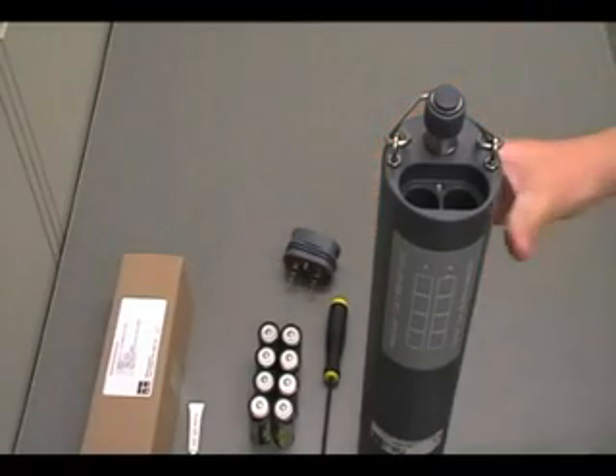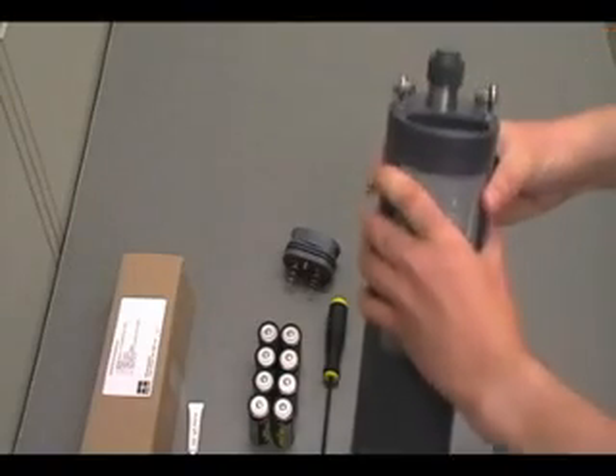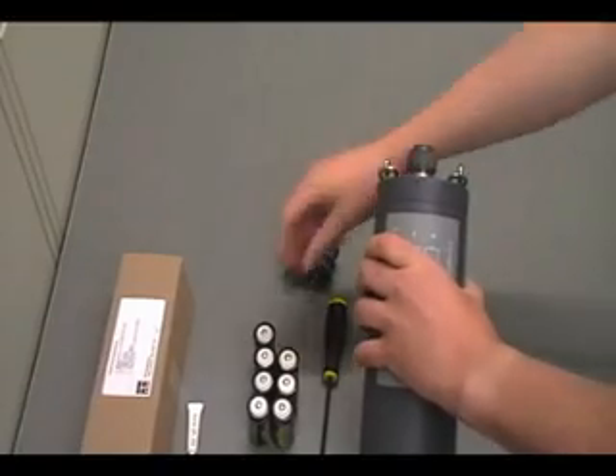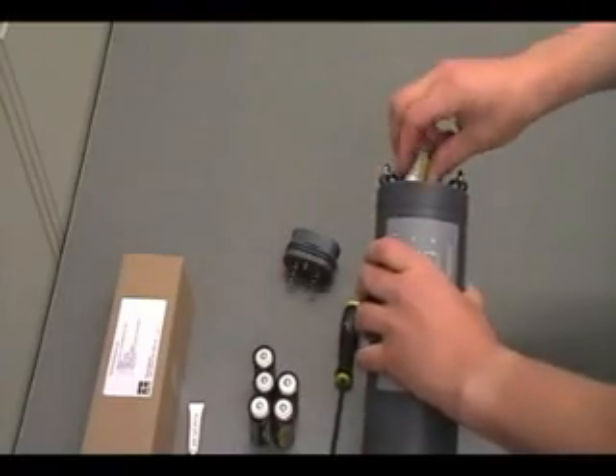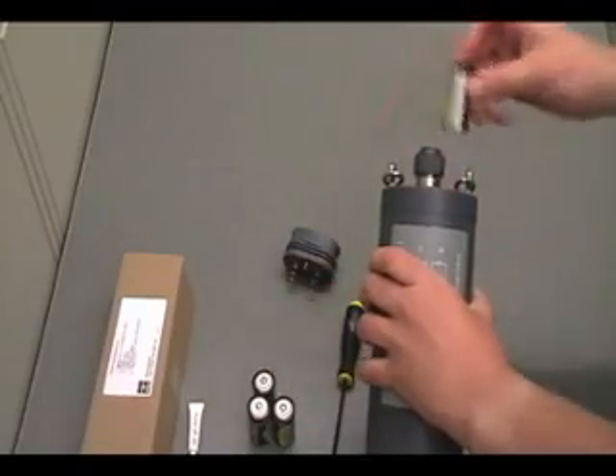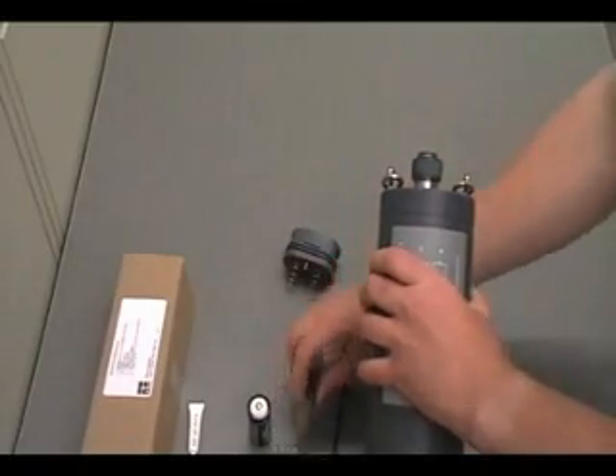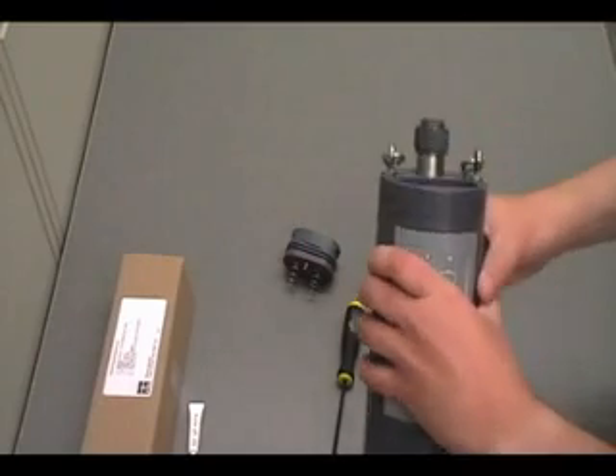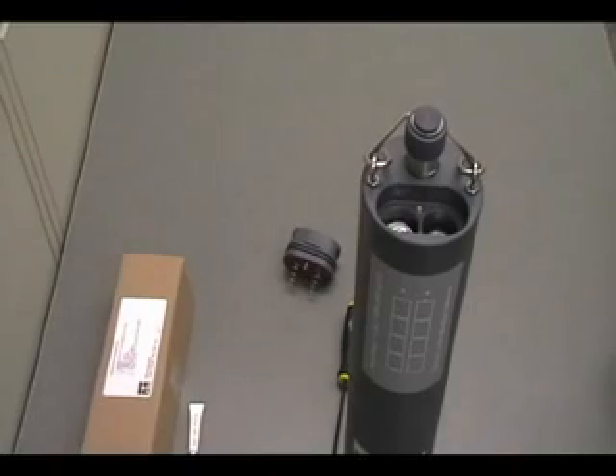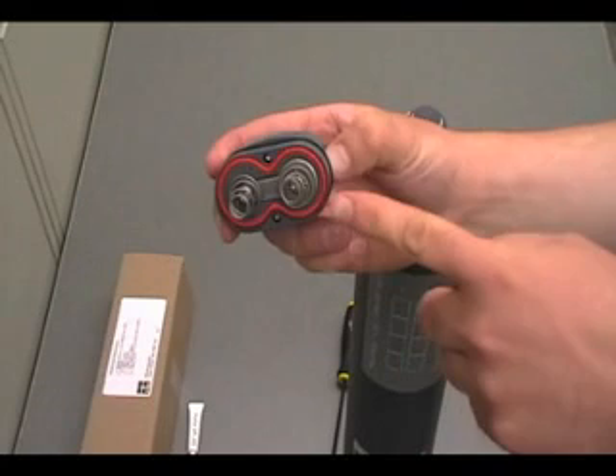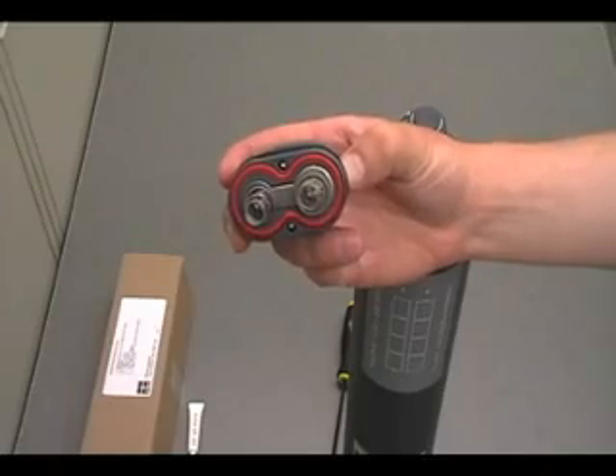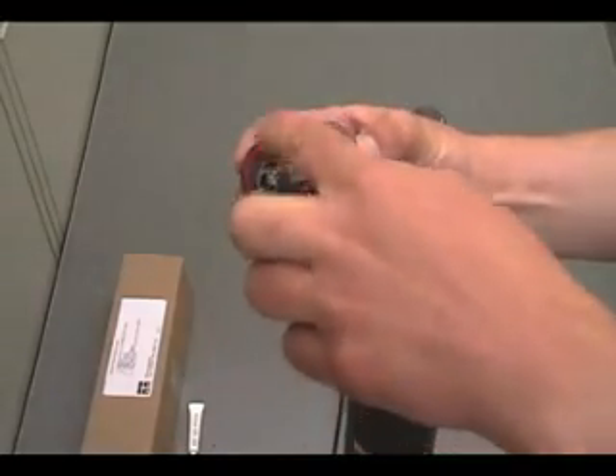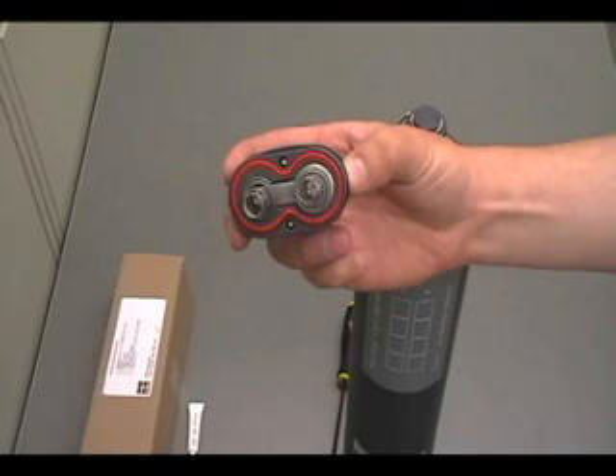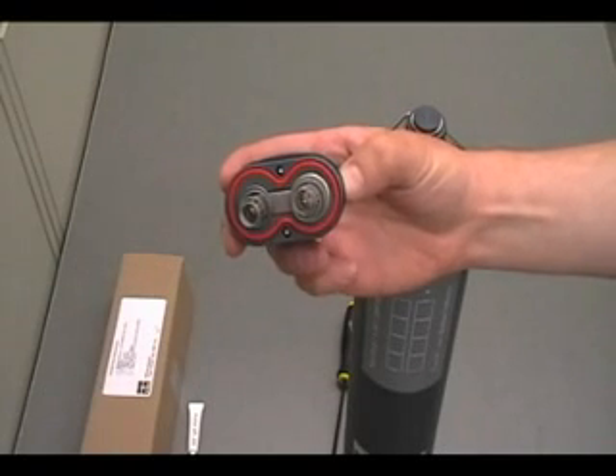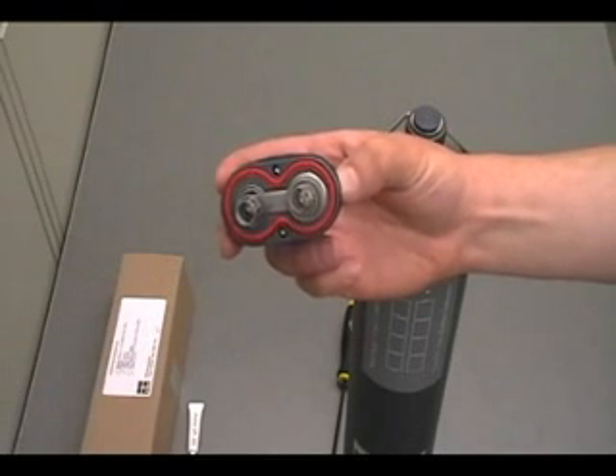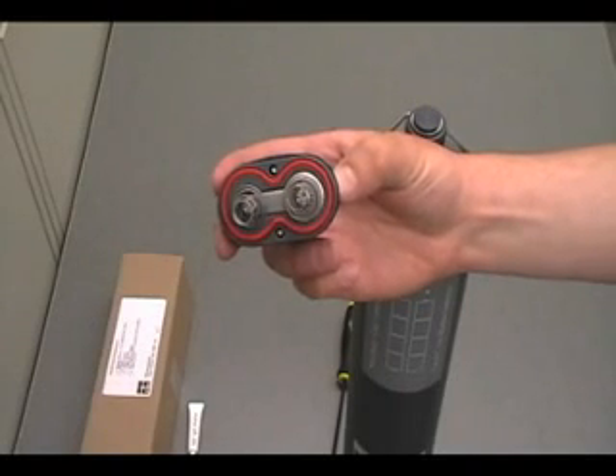Install the batteries as shown on the guide. Ensure that they have the proper orientation. Step 3. Before replacing the lid, it is important to ensure that the orange O-ring is seated completely within the groove on the underside of the lid. Press around its edges to make sure it is not popping out of the groove anywhere along its length. Small retaining tabs along the O-ring help keep it inside the groove. There is a detailed description of how to properly seat this orange O-ring on pages 219 to 220 of the YSI instruction manual. Do not lubricate the orange O-ring, but make sure it is clean.